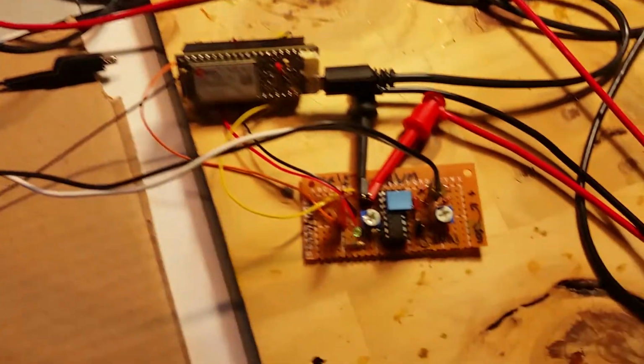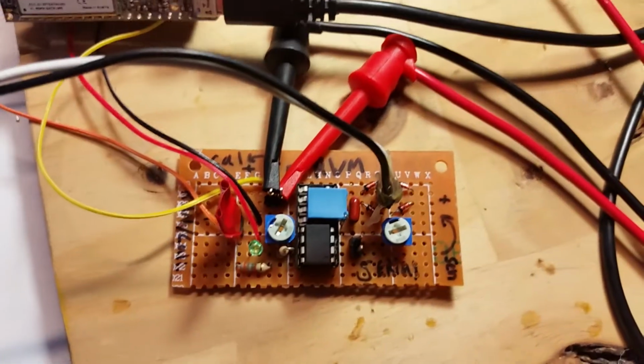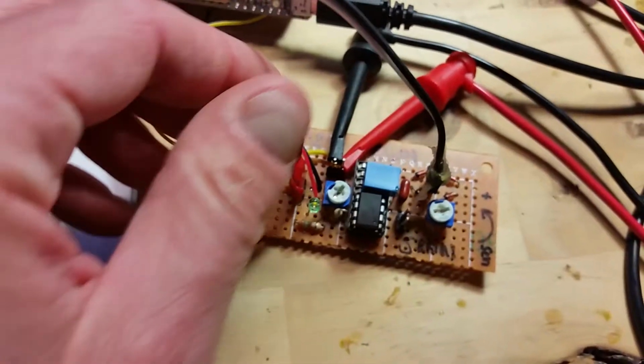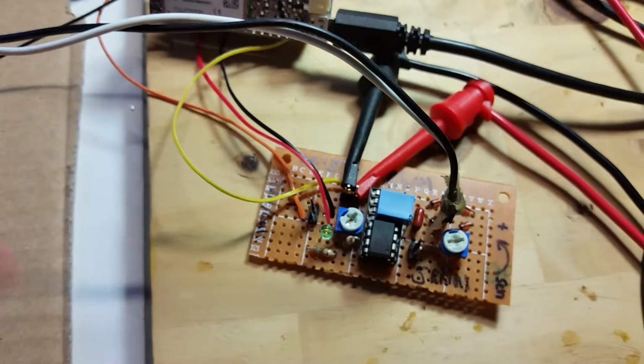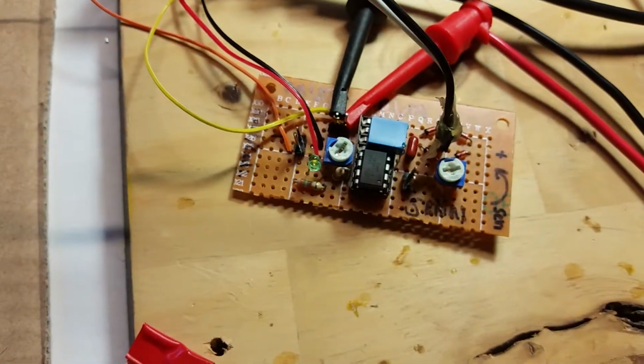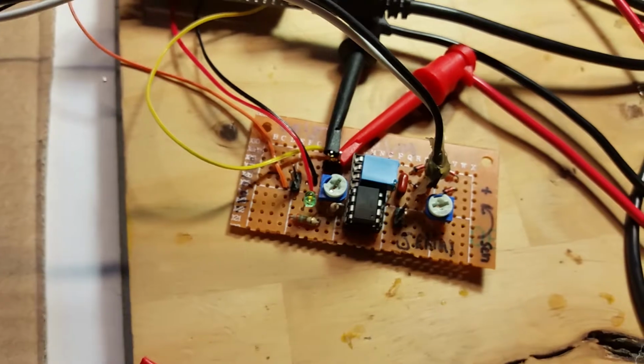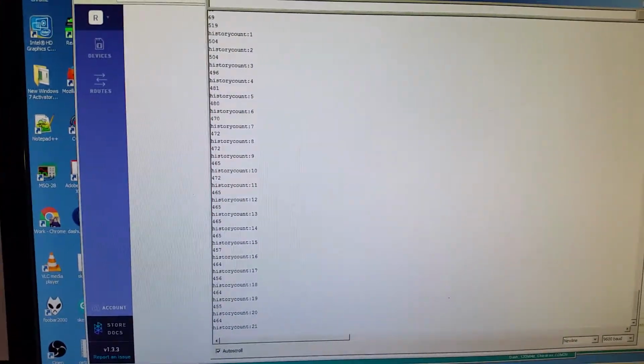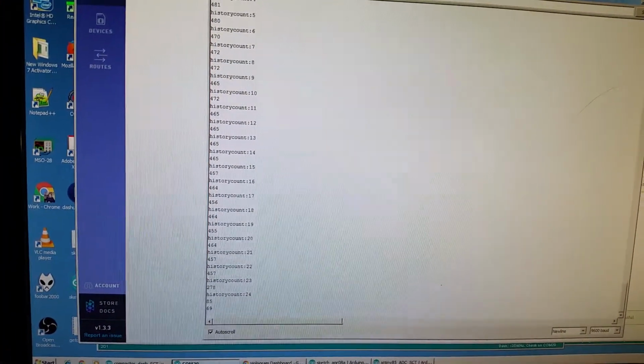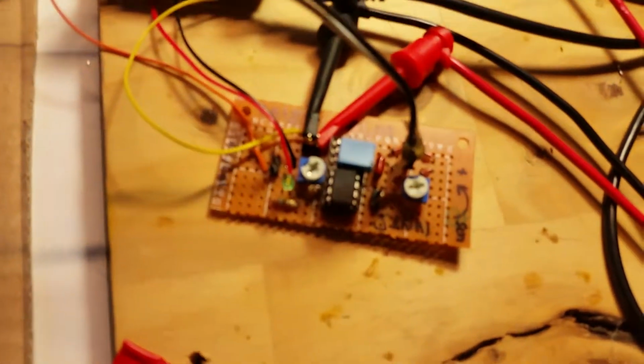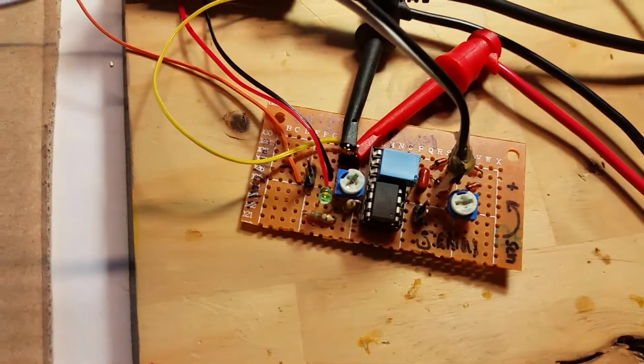I'm going to put together some documentation for calibration here. One other thing is that there's this right here. We can actually pull this off, and if we pull this off and we turn on the heater for a while, it still collects data. Let's see here, we've got data still being sent. But if I turn it off, it will dump the history, but it doesn't send it to the cloud. So if you're going to be doing calibration, that kind of thing, then you want to keep this off.